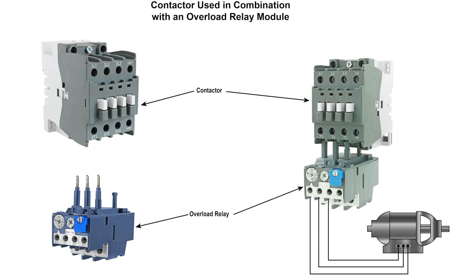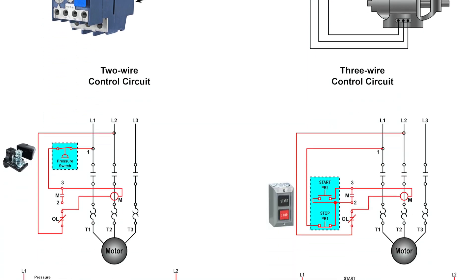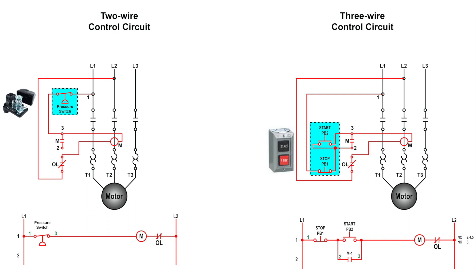Two-wire control circuit is commonly used in applications where the operation is automatic, and the pilot device starts the motor automatically as needed. A three-wire control circuit is similar, except it has an extra set of contacts used to seal in the circuit. Generally, these types of circuits are controlled with a start/stop push button.